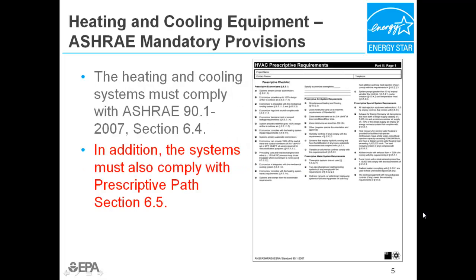Heating and cooling equipment. In the Performance Path webinar, you were introduced to the mandatory provisions of ASHRAE 90.1. Chapter 6 covers heating and cooling equipment. Section 4 of most ASHRAE chapters outlines the mandatory provisions determined by ASHRAE. Meeting those provisions is one of the requirements of this program, regardless of path selected.